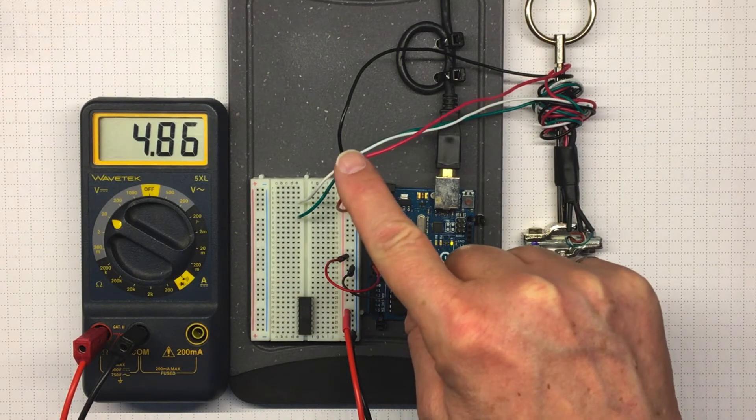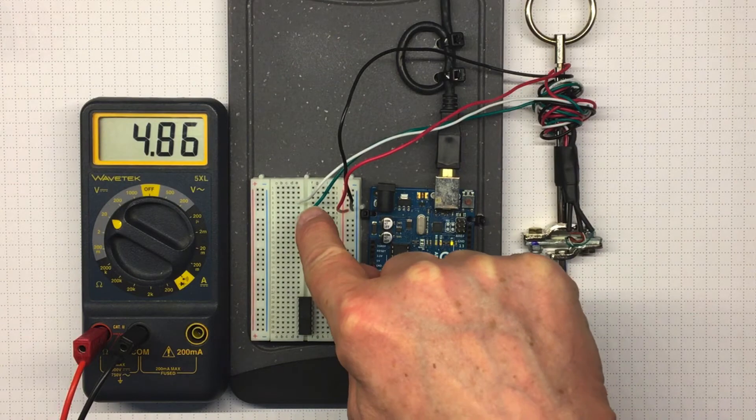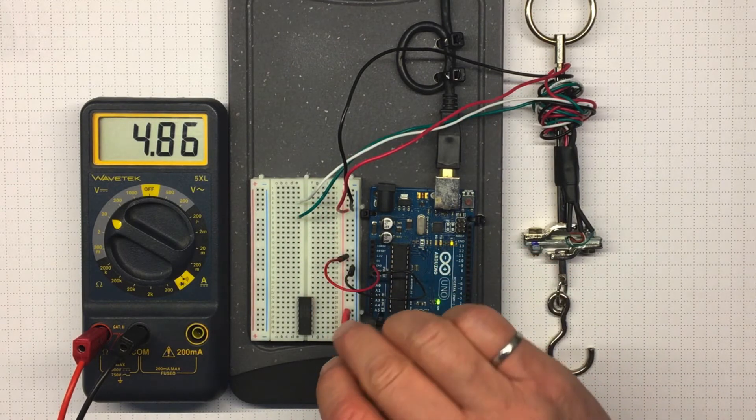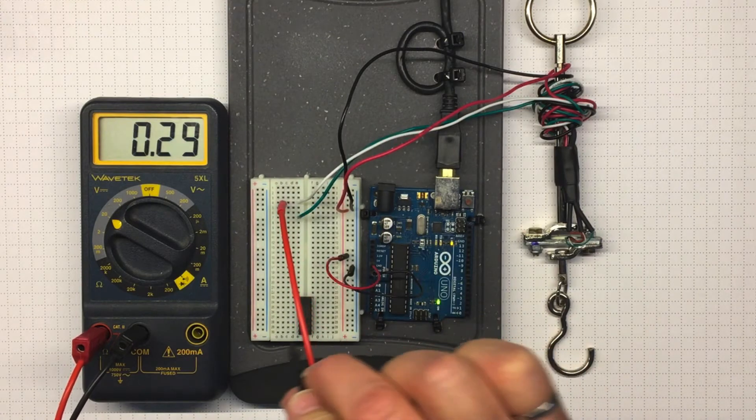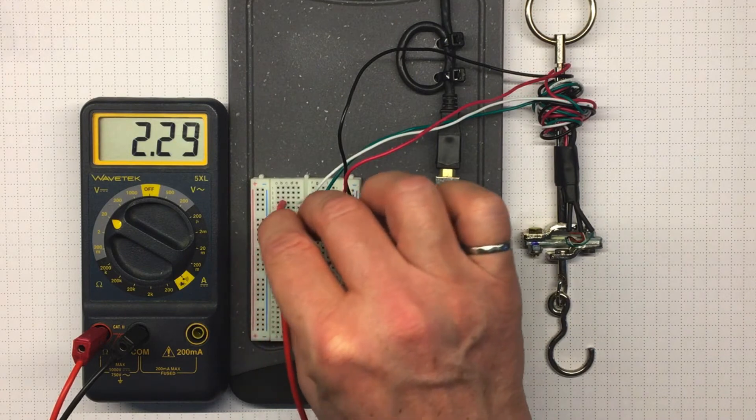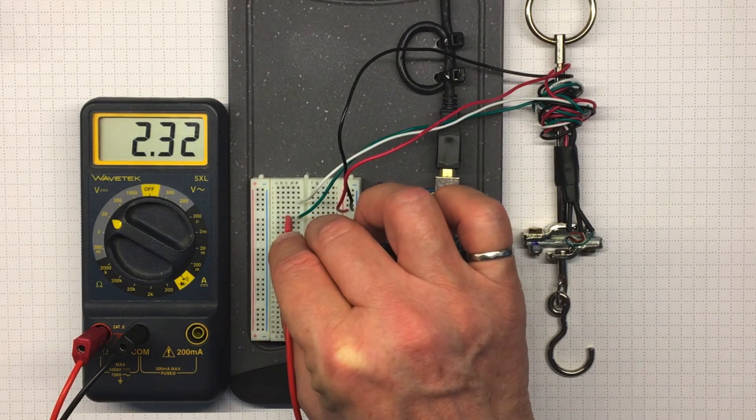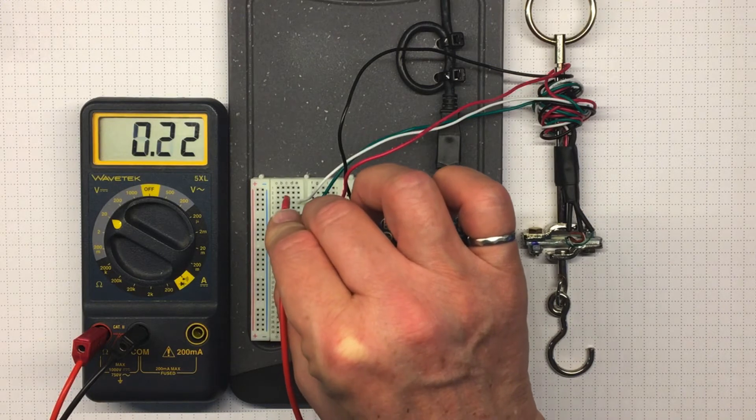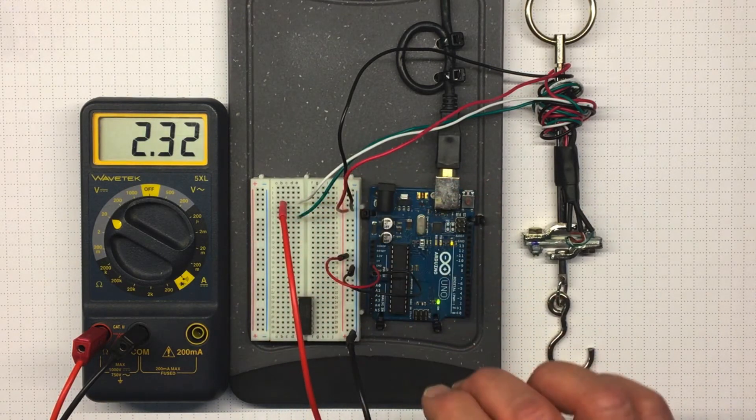So if I've got 4.86 volts DC going out to the load cell, what have I got coming back? Let's measure the absolute voltage on the white wire and the green wire. About 2.3 on each of them. So they're close to, but not exactly the same.